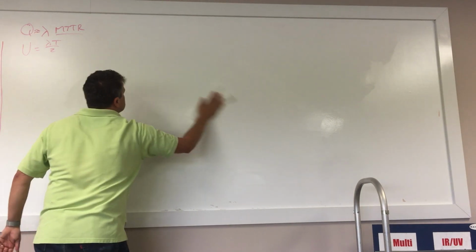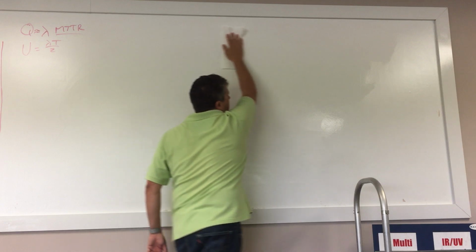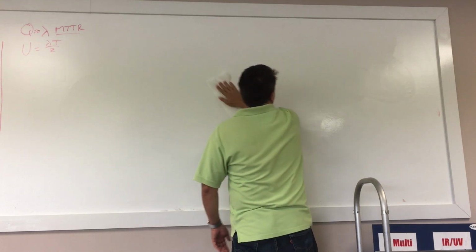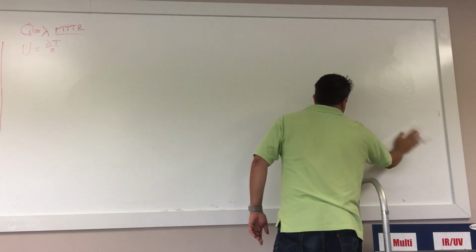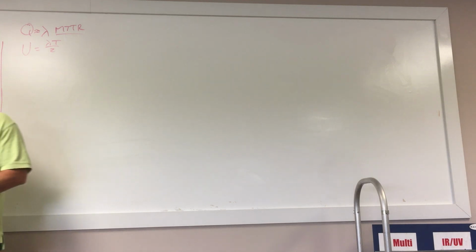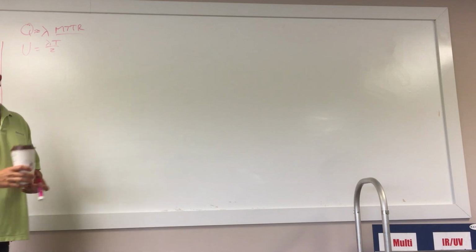That term is either going to be called the common cause term or the beta factor term, and it shows up appropriately in 1 out of 2 voting and 2 out of 3 voting. It shows up, in my opinion, inappropriately for 2 out of 2 voting.